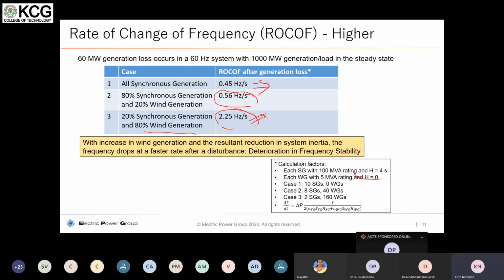And all these things are calculated using a simple formula, as shown here. You can see that with the wind generation, this whole term will become 0 because the inertial support from renewables is 0, and therefore dF by dt will go up for a given imbalance. When the wind or solar generation happens, there is no support from them, and hence for the imbalance that happens in the power, dF by dt has to go up. There is no other way, basically. So therefore it impacts the ROCOF of the system.